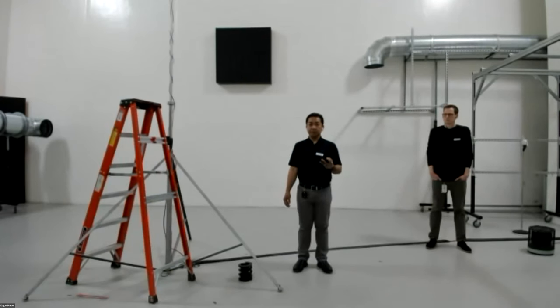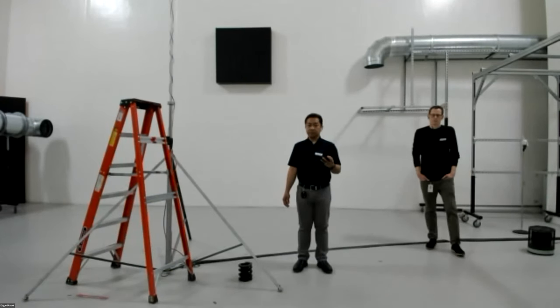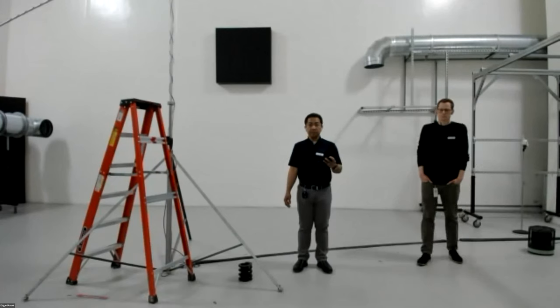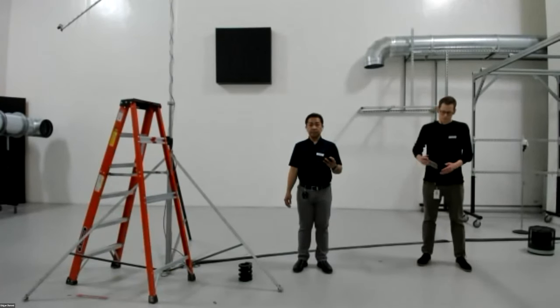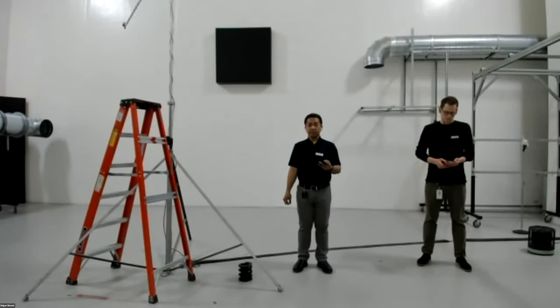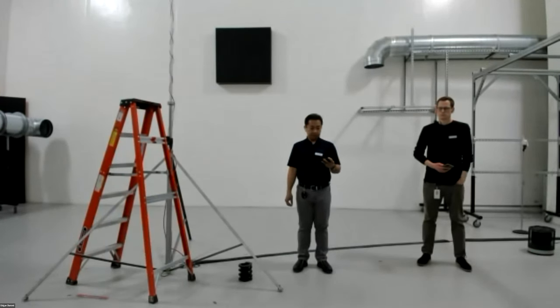Okay. Yeah, the room comes in handy a lot more than just silencers. We use it for testing things like fan powered terminal boxes. We'll put it in the room and measure radiated noise and calculate sound power. We'll also use it for things like hydronic chilled beams to measure discharge noise, diffusers, grills, registers, air moving devices. It's very versatile and you kind of need that echoey reverberant space to do that.